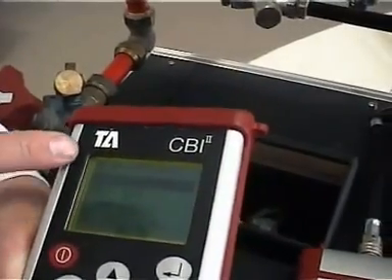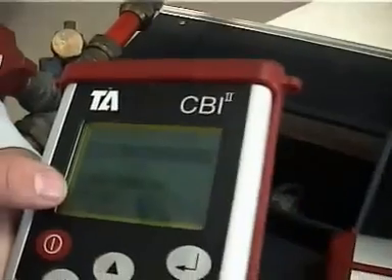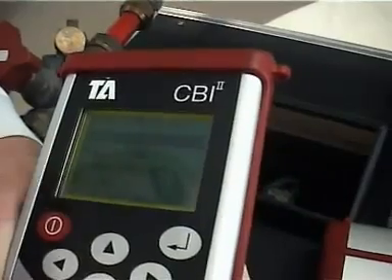It's came up with the flow rates on it, and it tells us our valve number one to achieve the flow rate of 0.06 litres a second must be set to 1.9. At this stage, we can scroll through and see what our other valves must be changed to. Valve number two needs to be set at 2.7 turns. We go around and we readjust all our valves now to the sequence.